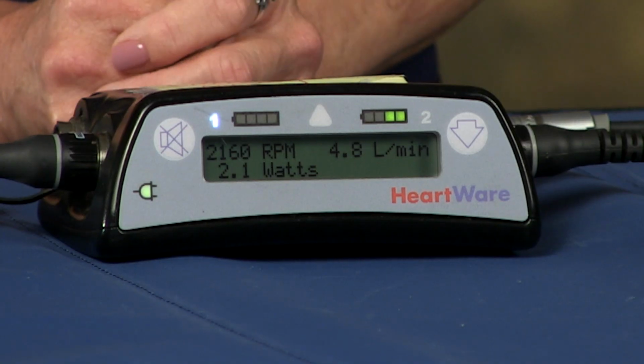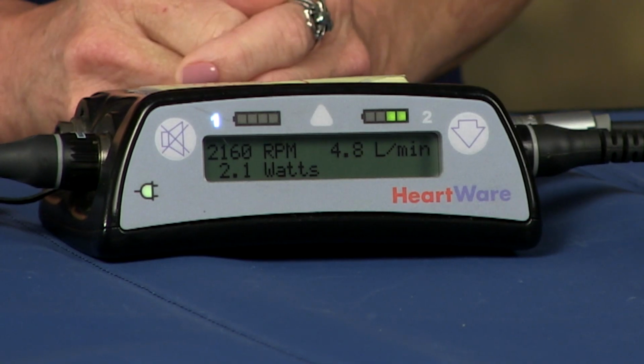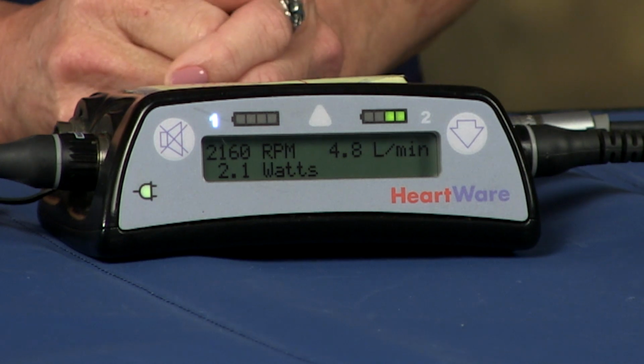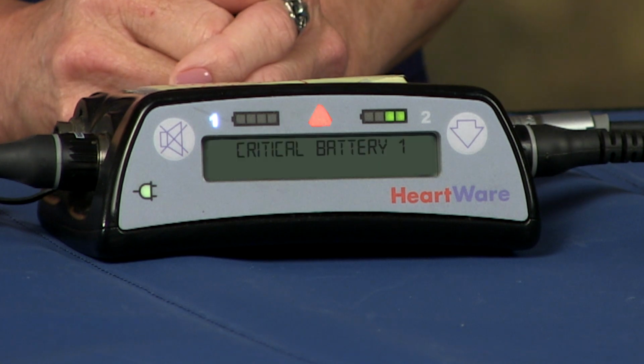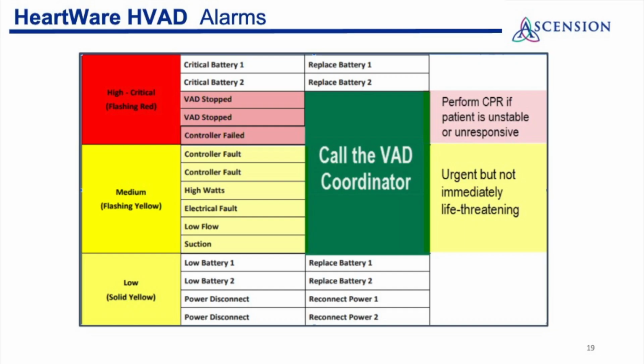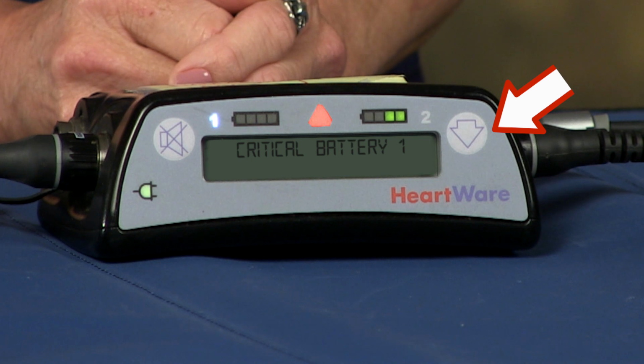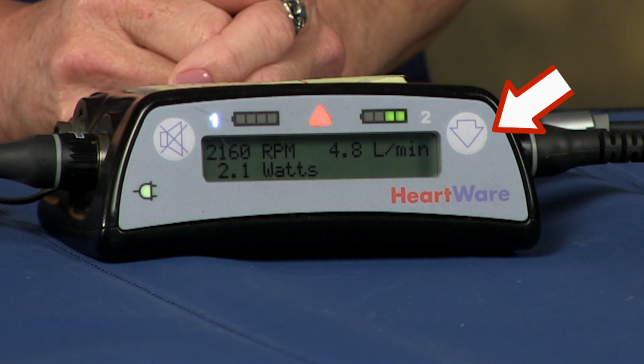When the HVAD pump is running, the VAD numbers will always be displaying speed in RPMs, flow in liters per minute, and power in watts. If an alarm occurs, the triangle here will illuminate with a message on the screen. For battery-related alarms, change the batteries. For other alarms like controller fault, high watts, low flow, call the VAD coordinator. If they ask for the VAD numbers while the alarm is occurring, press this arrow down button and the VAD numbers will reappear.